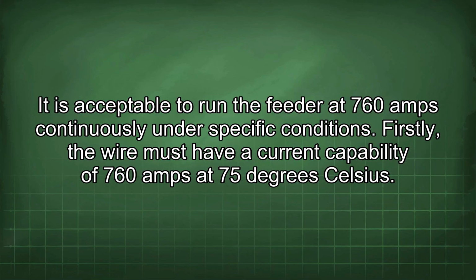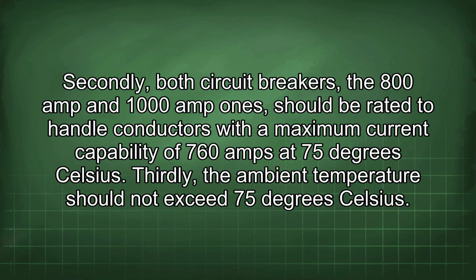It is acceptable to run the feeder at 760 amps continuously under specific conditions. Firstly, the wire must have a current capability of 760 amps at 75 degrees Celsius. Secondly, both circuit breakers, the 800 amp and 1000 amp ones, should be rated to handle conductors with a maximum current capability of 760 amps at 75 degrees Celsius. Thirdly, the ambient temperature should not exceed 75 degrees Celsius.